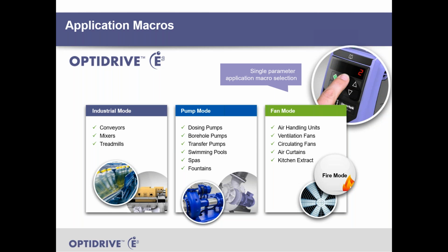And then we have fan mode, so air handling units, ventilation fans, circulating fans, air curtains, and we have quite a high install base, or quite a large install base of kitchen extraction with these also. So the industrial extraction units for industrial kitchens. And to choose this mode is very, very simple. It's just 1 parameter, and then that sets some preset defaults in the drive that are ideally suited for the 3 different modes.